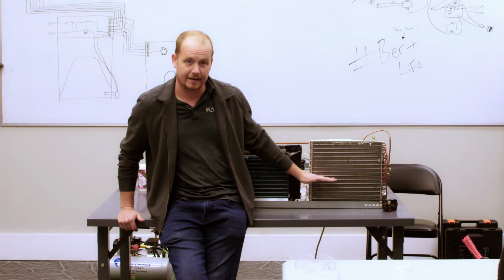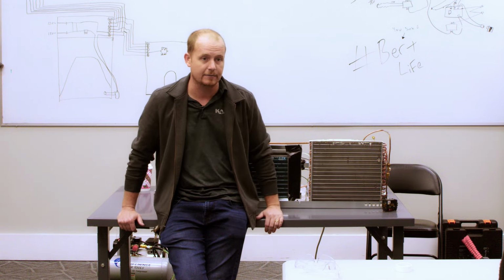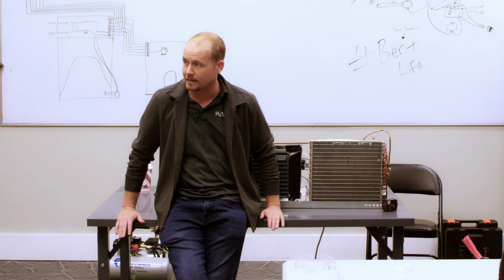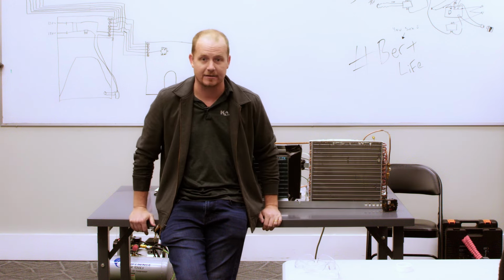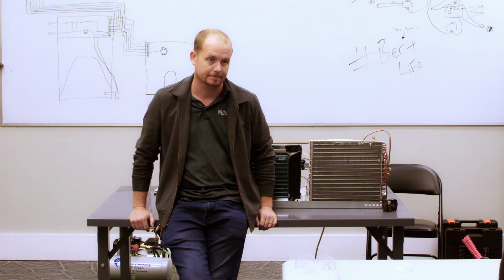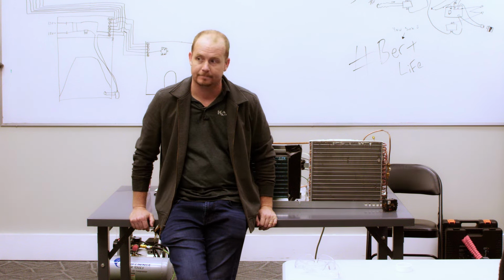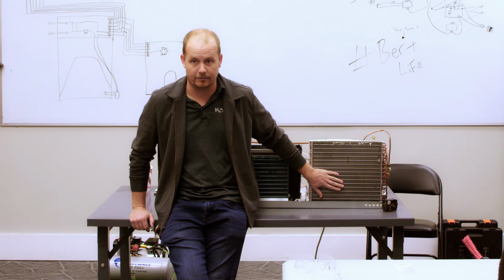as you stack more liquid in that condenser, you reduce the amount of condensing area, and that drives your head pressure up because now the area that's available for heat rejection is decreased, because we have a limit to how cold that liquid can get, right? There is a limit. There's a stopping point. That liquid can only get so cold in the condenser. And what is that stopping point? No, it's not freezing. What is your condenser rejecting its heat to? Outdoor air, right? So can your condenser by itself get the liquid colder than the outdoor air?